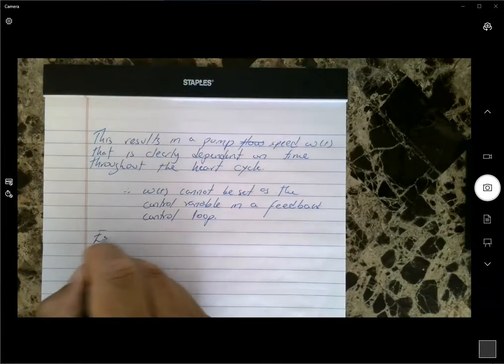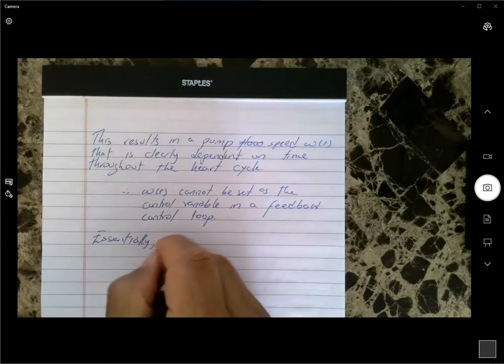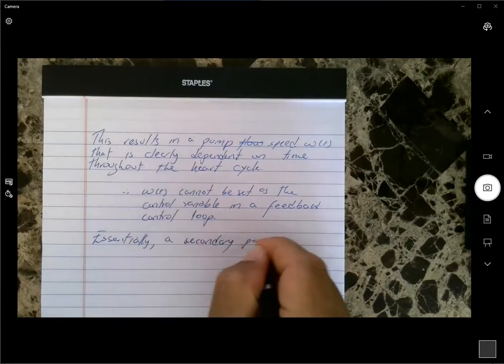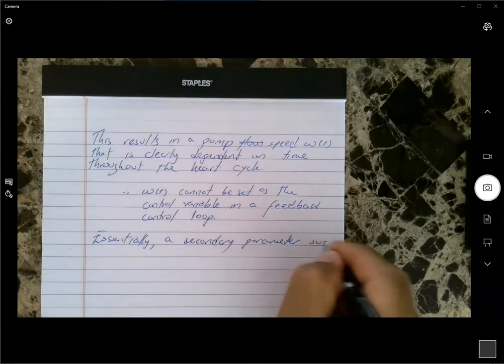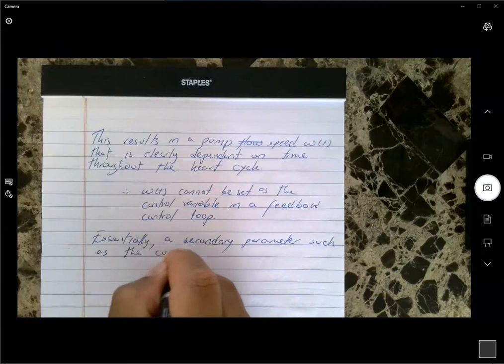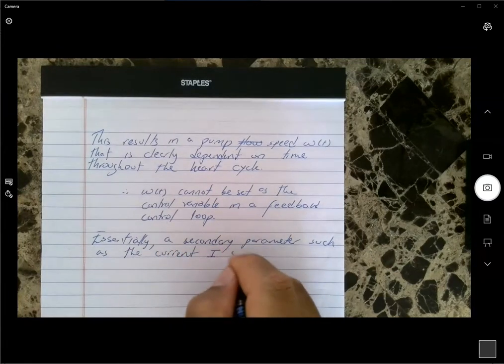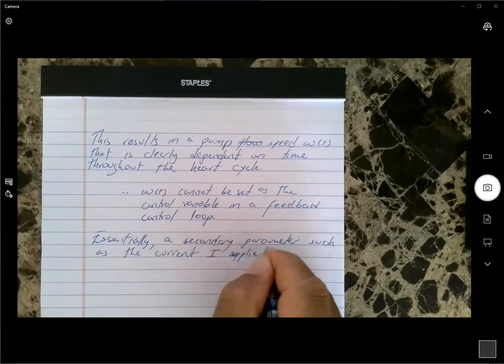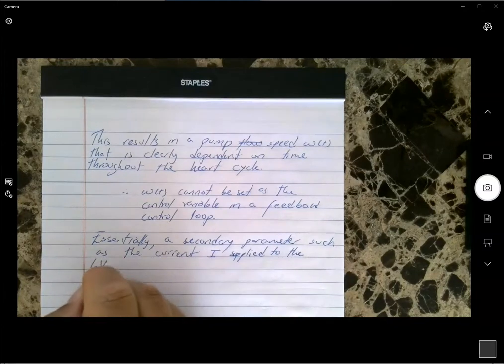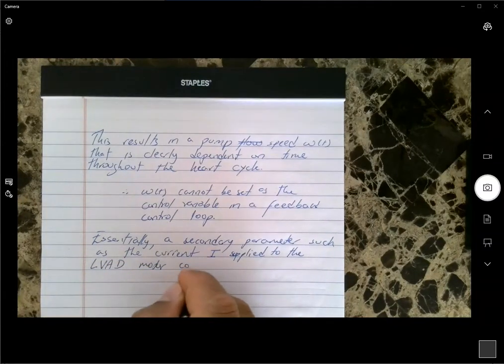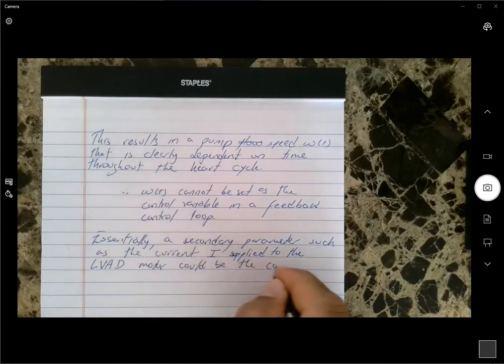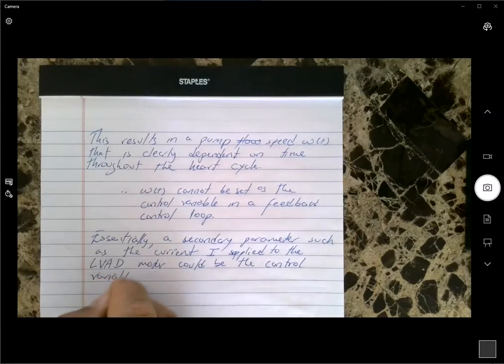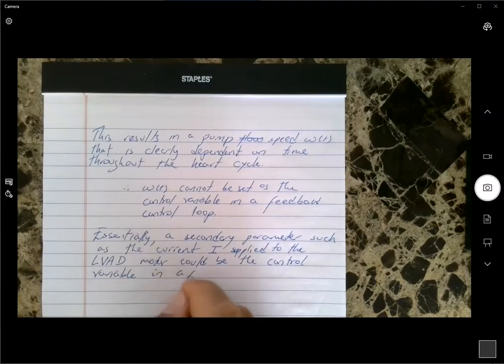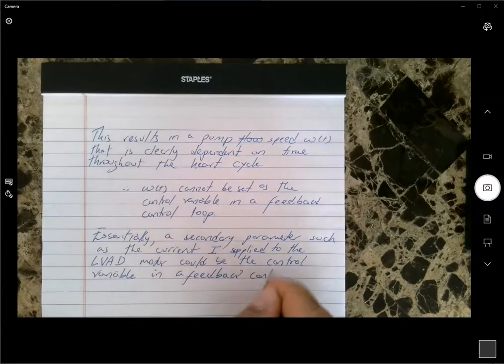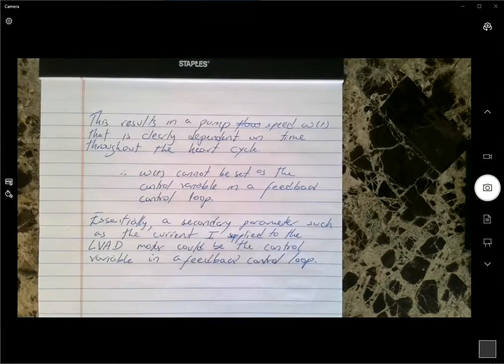So essentially, a secondary parameter such as the current I supplied to the LVAD motor could be the control variable in a feedback loop, because that's one that we can alter directly by, you know, a potentiometer or adjusting the dial on the pump itself.